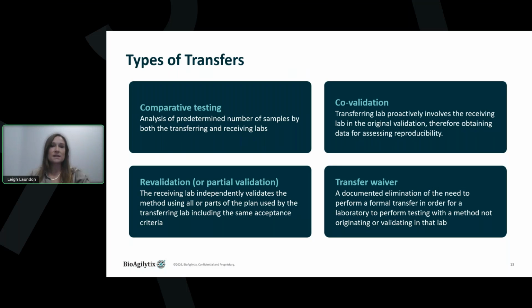Another less common and less desired option is the transfer waiver. This is not normal for a complex assay such as a bioassay or any other cell-based assay, but if you are doing some sort of compendial testing where the protocols are very basic and both labs have individuals trained in that platform, you could opt for a transfer waiver to waive the wet lab work portion of the transfer process.